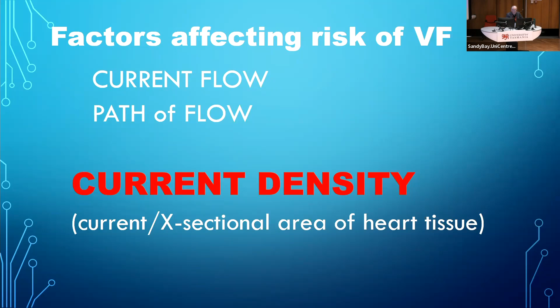The next critical factor is the duration of the current flow - how long it flows for. For 50 hertz exposure, VF is almost unknown if the current flows for less than about 20 milliseconds. This is the target time for most of our current earth leakage protection devices. If you do the math, you'll see that 20 milliseconds is actually the duration of one complete AC cycle - and that's actually the clue to the mechanism of VF itself.